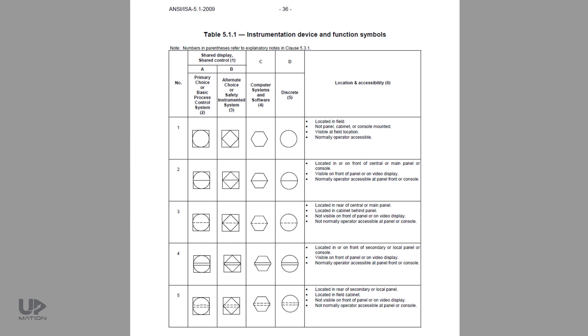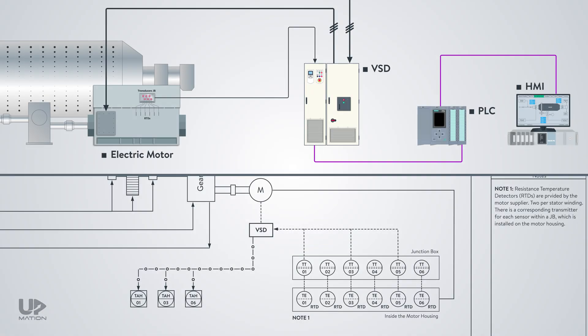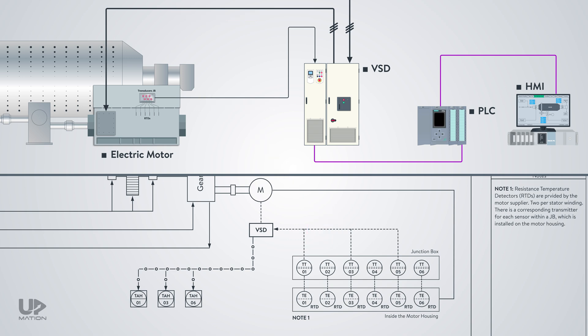But why and how did I choose this symbol among the other 20 symbols in this table? Honestly, you might not get clear data out of this table unless you read the whole ISA 5.1 document. Therefore, I will summarize the most important points of this table during and at the end of this video. You should already know that dashed lines are used for electric signals or electrical connections, but to show the communication links or a network bus between devices and HMI objects, we should use this type of connection line.